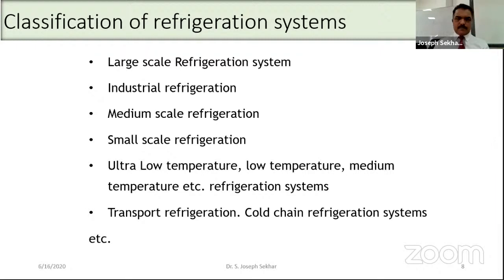Based on temperature, we have ultra low temperature, where if the temperature is -80, -100 and so on, it is mainly used for vaccine preservation or in the medical field. Low temperature refrigeration is around -60, -50, mainly for preserving meat products, ice creams, and so on. Medium temperature systems are for air conditioning, water cooling, and so on - these are the different types based on temperature.